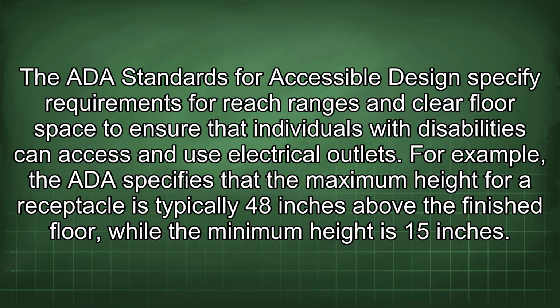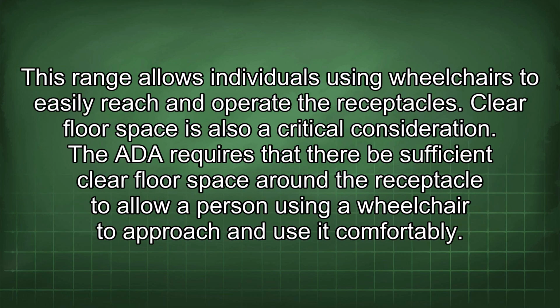The ADA specifies that the maximum height for a receptacle is typically 48 inches above the finished floor, while the minimum height is 15 inches. This range allows individuals using wheelchairs to easily reach and operate the receptacles.